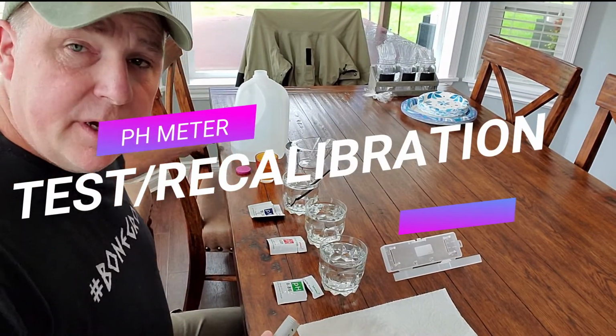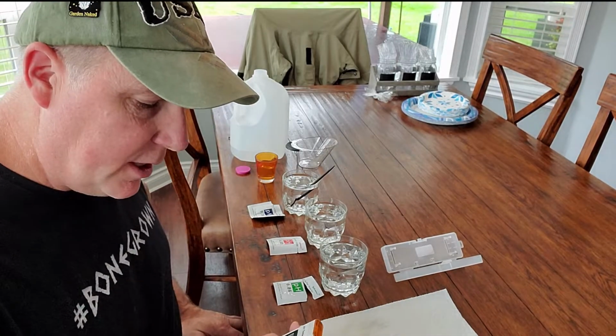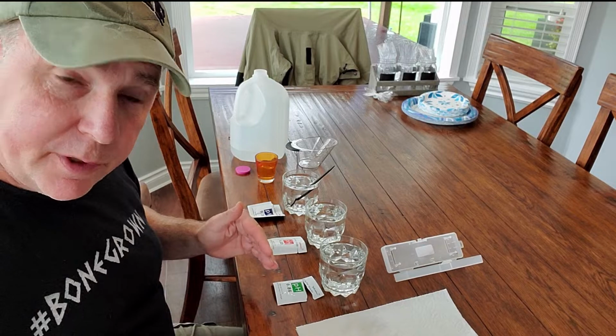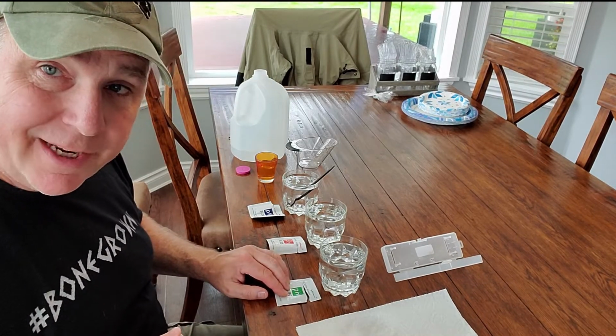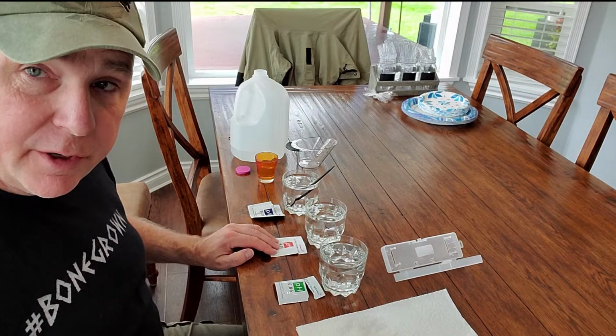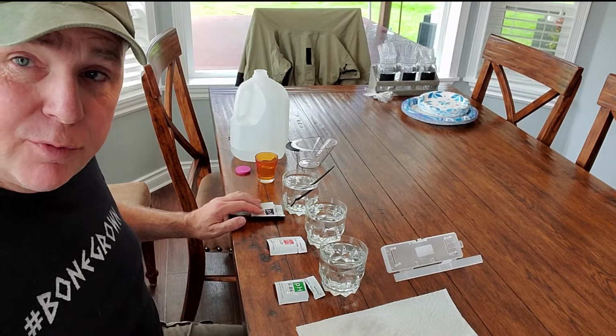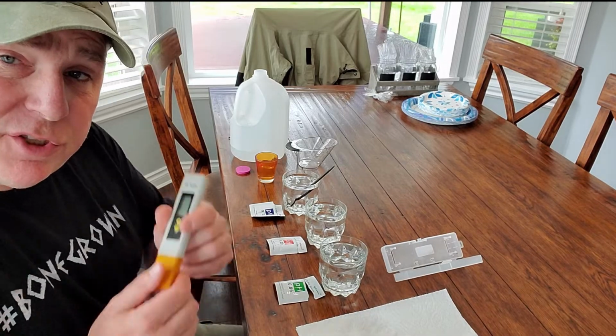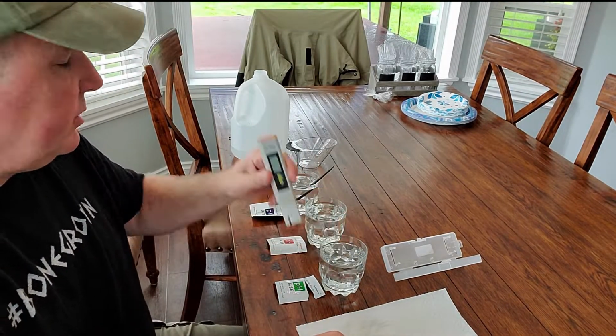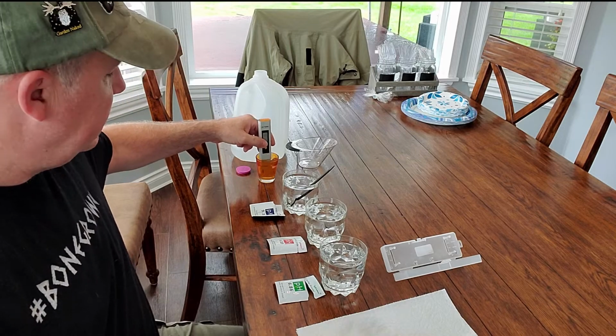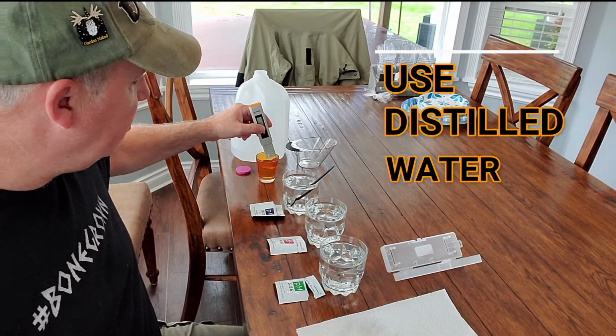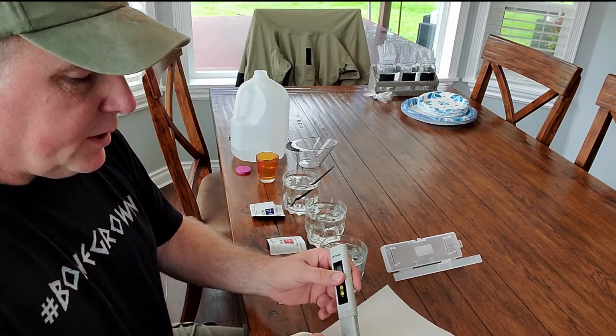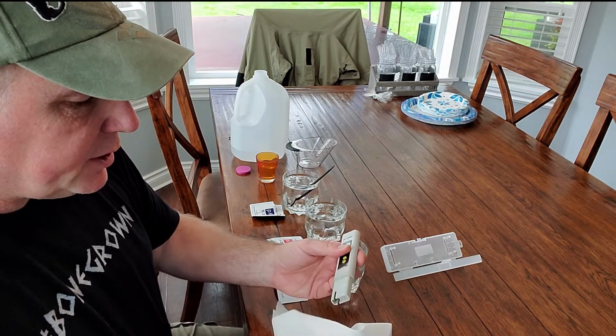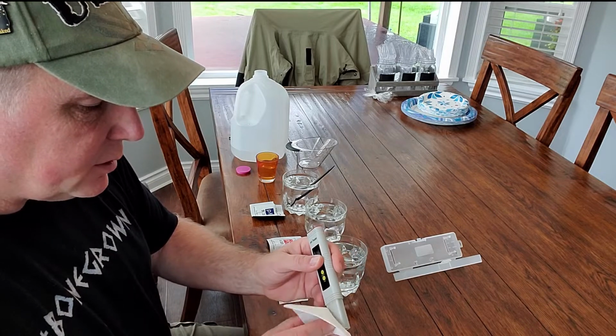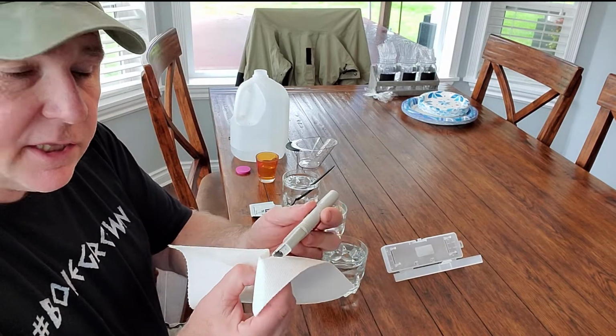And again, all of these cups have been filled with 250 milliliters of distilled water and have been given the appropriate solutions. On the first one, a 6.86, the next one, a 4.0, and the third one is a 9.18. Now, when you do an initial test, you're going to take your meter out, make sure that it's clean. You want to make sure that your instrument's always clean before you test it. You shake it a few times, and then what you're going to do is dry it off as best you can. Trying to get everything dry, just like that.